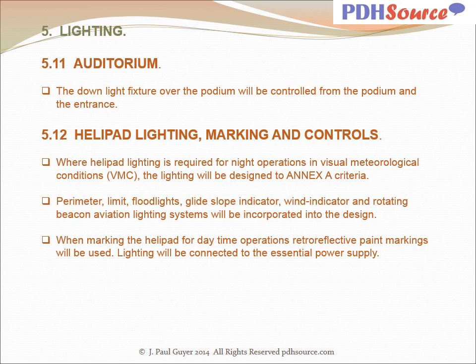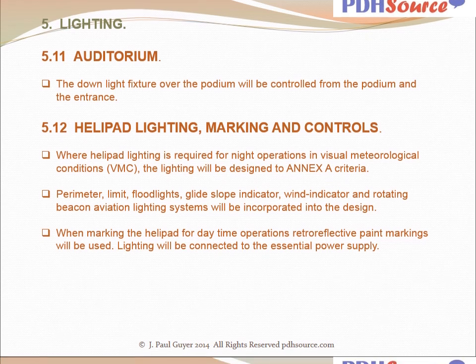The downlight fixture in auditoriums over the podium will be controlled from the podium and the entrance. At helipads, where helipad lighting is required for night operations in visual meteorological conditions, the lighting will be designed to Annex A criteria. Perimeter lights, floodlights, glide slope indicator, wind indicator, and rotating beacon aviation lighting systems will be incorporated into the design. When marking the helipad for daytime operations, retroreflective paint markings will be used. Lighting will be connected to the essential power.